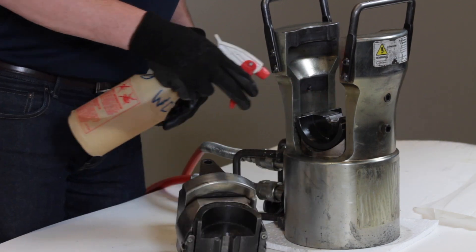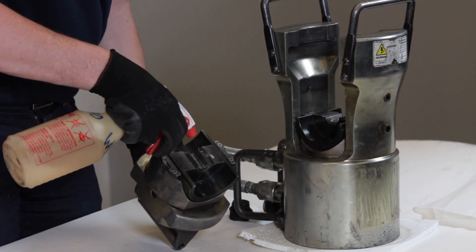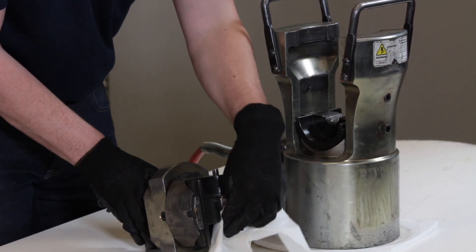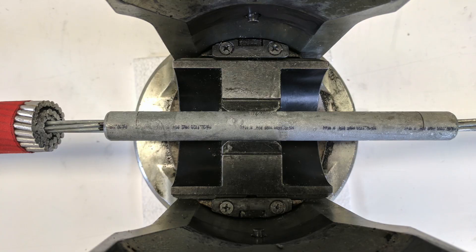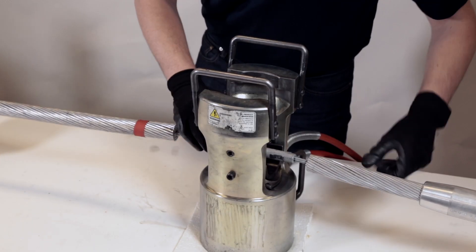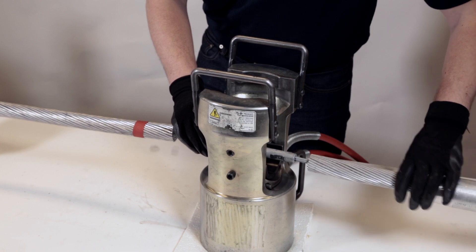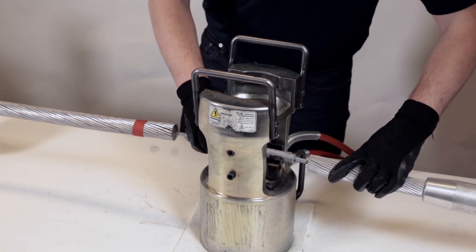Install, clean, and lubricate the correct compression die. This is marked on the core splice tube. Insert the assembly into the press with one side of the center nurl lined up with the edge of the die. Before compressing, double check that the ends of the splice tube are lined up with the marks on the core strands.